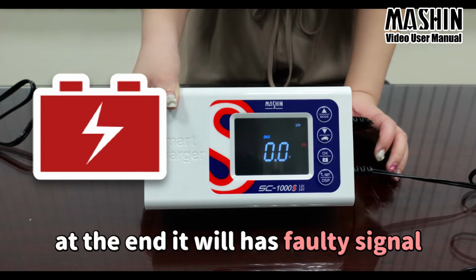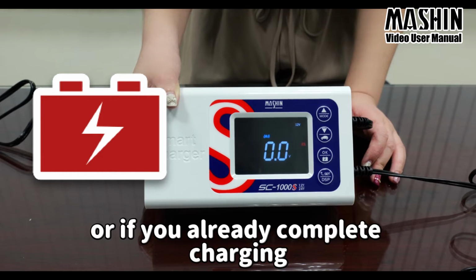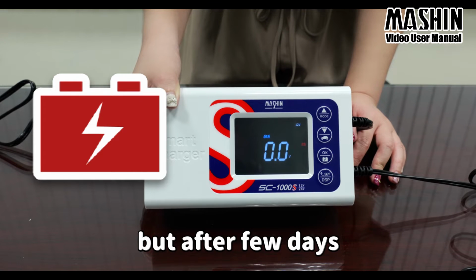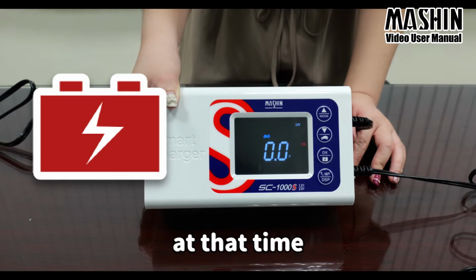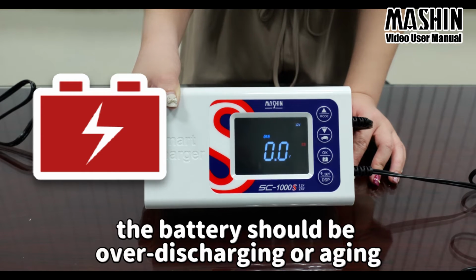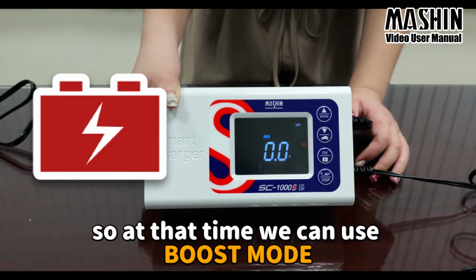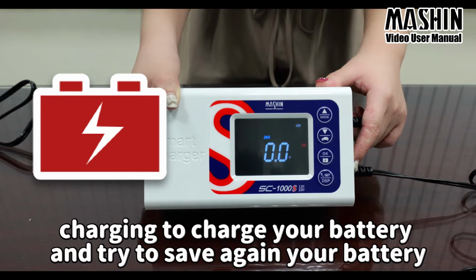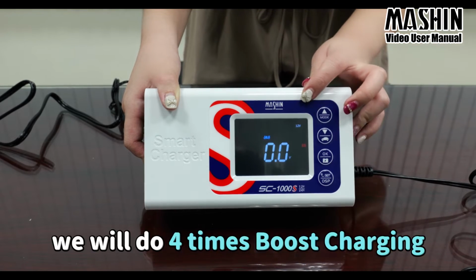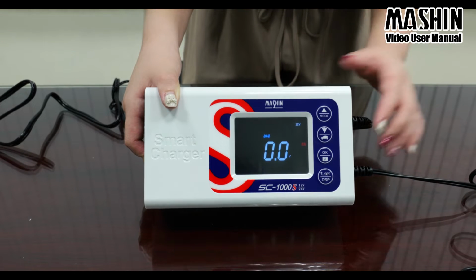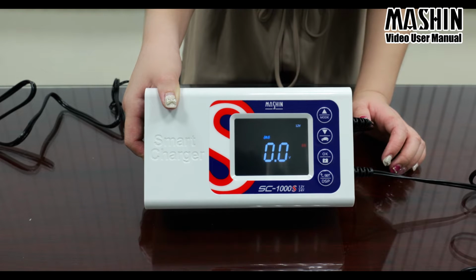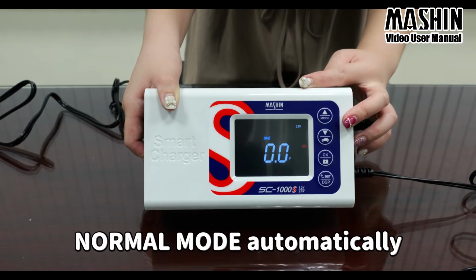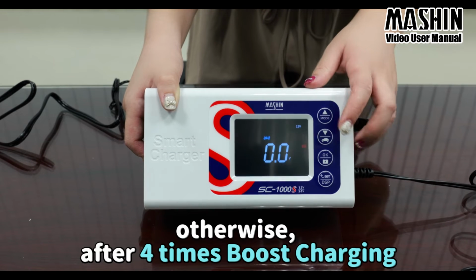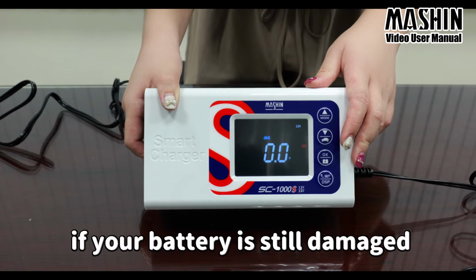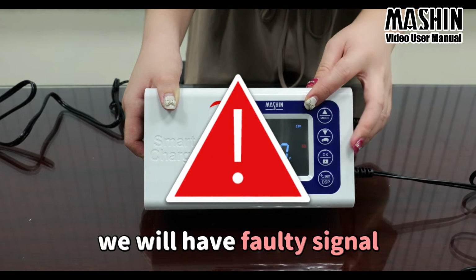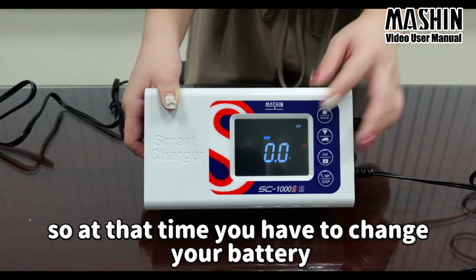At the end there's a faulty signal. If you already completed charging, but after a few days your battery voltage is low, at that time the battery should be over-discharging or aging. So we can use boost mode charging to try to save your battery again. With boost charging, we do 4 times boost charging. If each time your battery can go back to normal condition, it will go to normal mode automatically. Otherwise, after 4 times of boost charging, if your battery is still damaged, we will get the faulty signal, meaning you have to change your battery.